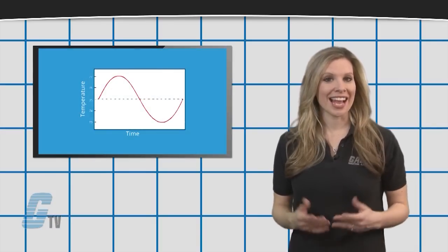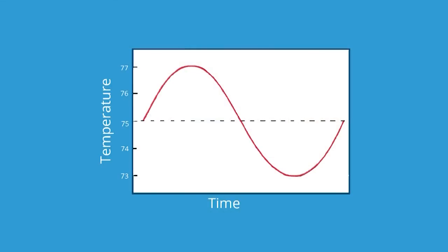Using a thermostat as an example, the desired temperature could be 75 degrees, but the hysteresis could be set so that cooling begins at 77 degrees and stays on until set to 73 degrees.